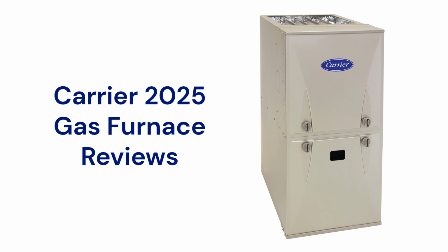This brand is only sold through dealers in the USA and Canada, and the furnaces are backed by a pretty good guarantee, but it does not include unit replacement in case of heat exchanger failure, which has become the industry standard. They use aluminized steel primary heat exchangers, which resist corrosion but are not as durable as brands that use stainless steel.